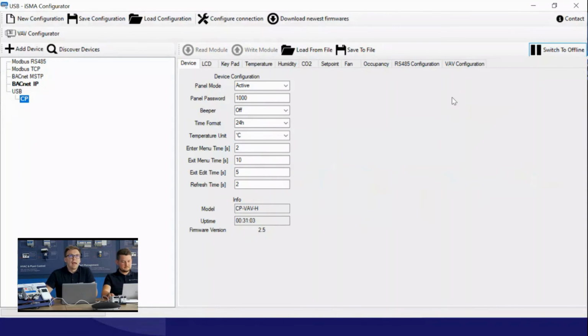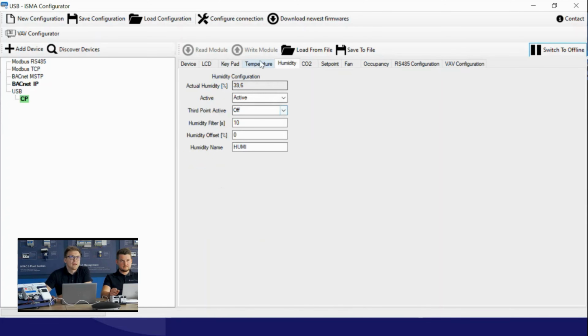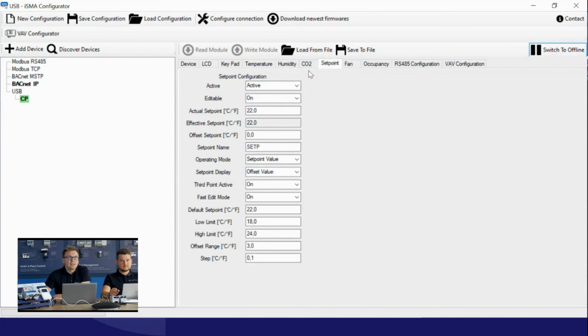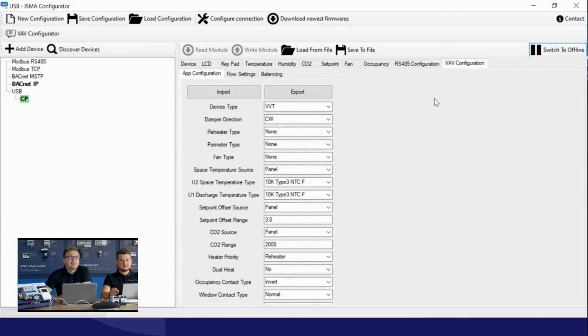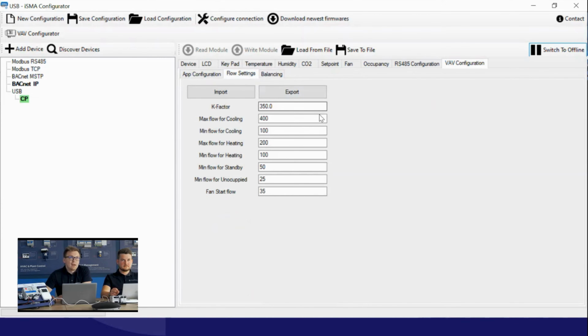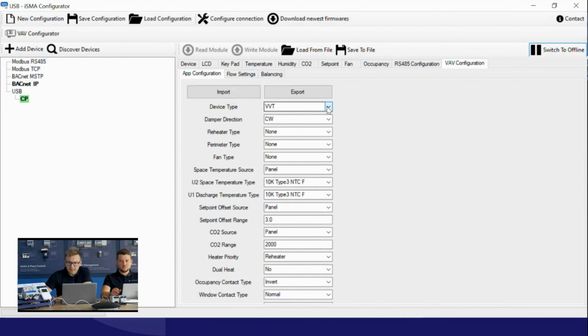I will switch to online and I've got all the tabs responsible for the CP panel configuration. You can see that I've got a CP VAV model with the humidity sensor, so I can measure the humidity. I can set all the basic settings for the CP panel. And I've got one additional tab, which is the VAV configuration. Here I can make all the step configuration about the application configuration, flow settings, and balancing. And you can see that the K-Factor, which was set by me using the CP panel, was written in the iSMA Configurator.